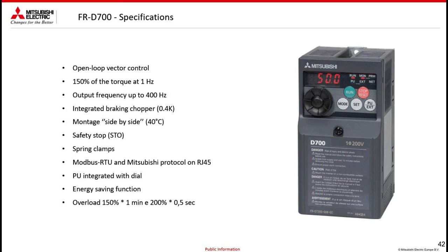It can be integrated with a PU, can be integrated with a dial, so the screen with a wheel. Energy saving function, there is a parameter with which this function can be activated, but to use it is necessary to carry out analysis, since if there was a variable load, the energy saving function would not be suitable, as it could create oscillations.